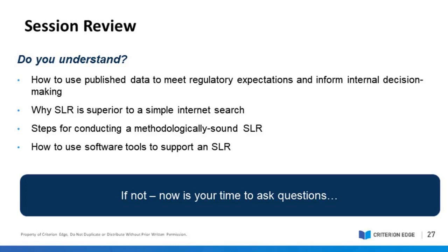The issue of reproducibility, I don't think any notified body expects a 100% match from one search to the other search. I have heard stories that notified bodies will come in, or before they come in to audit or review CERs, they will pull the CER and rerun the search based upon the methodology that you describe in the document. So I think that's the bigger key here, that they're not going to want to see a one-to-one match of the 600 articles that you pulled on that search.